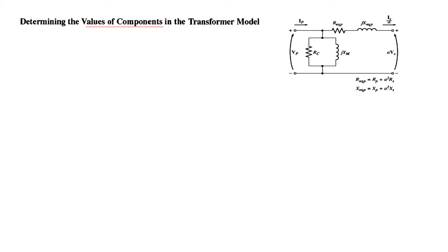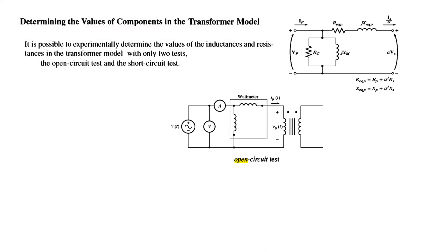Now, we need to determine the values of the components in the model, all these values. So it is possible to experimentally determine the values of the inductances and resistances in the transformer model, with only two sets of tests. Number one is the open circuit test and the other is the short circuit test.